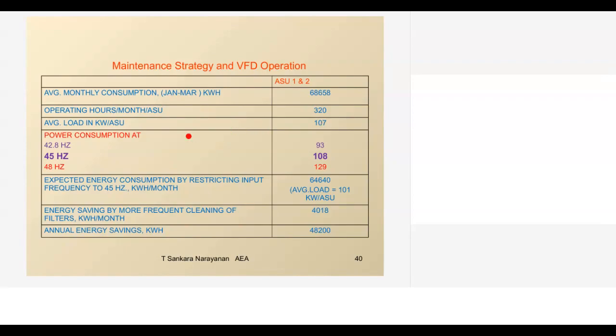When we started monitoring the frequency, we used to monitor every third day. Like that, we monitored for 3-4 weeks. Sometimes we have seen the fan is operated at 48 frequency also. Sometimes it is operated at 45, sometimes it is 42. That means when the filters are not cleaned properly, though I am having a VFD, I am operating the system at 48 cycles. So then we decided on the additional advantage: you are having a frequency display in the control panel. You have frequency as the guiding parameter.